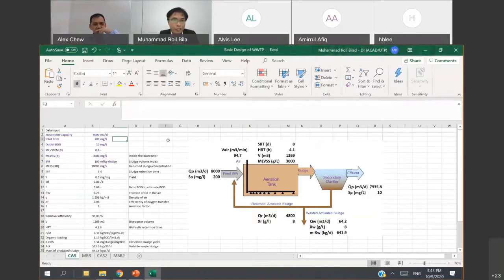If you have an inlet BOD, okay, I'm treating now the industrial wastewater, so my BOD is 2,000. So then it also gives you all of the parameters there. And then the parameters to operate the activated sludge are simple. The volume first. Okay, what will be the volume of my reactor? How much excess sludge do I need to waste? And how much of the sludge do I need to return, and of course what will be the volume of my reactors. So I will share this one. This is for activated sludge.